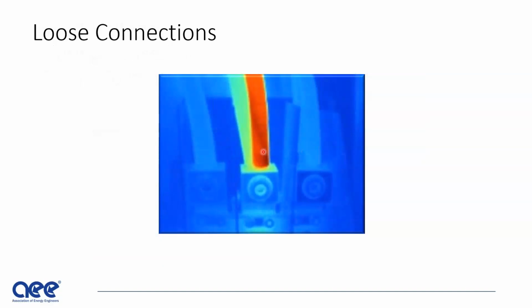And loose connections. You always want to be aware anytime you open up a panel or a box. The first thing we do is use an infrared gun to make sure that we're not dealing with loose connections. Very often we do see loose connections in panels and motors and other types of power connections, typically, and I can see in this case, a compression block mounting. Over time, due to the heating and cooling of the wire, you can get thermal expansion and contraction of the copper or the aluminum, and eventually that can loosen the connection. So for safety as well as proper preventive maintenance, you want to take precautions to look for loose connections whenever you open up any panel or any power connection box on a motor.